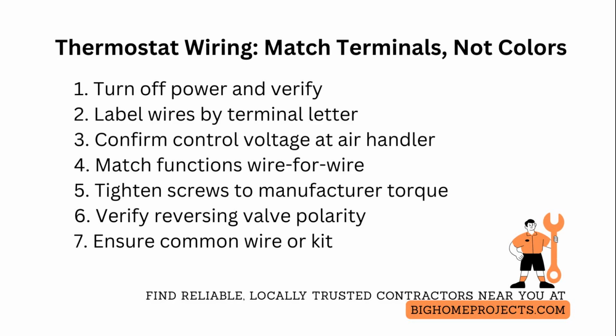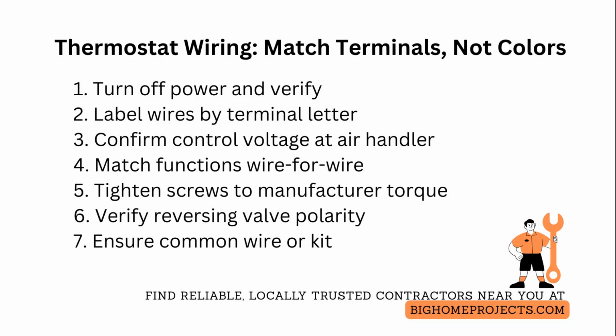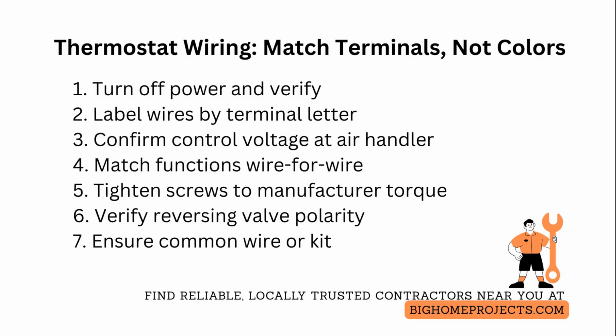Verify system type and control voltage at the air handler. Measure between common and the heating or cooling call terminal to confirm 24-volt alternating current or whatever your system uses, because many systems use different voltages or electronics that mimic common colors.